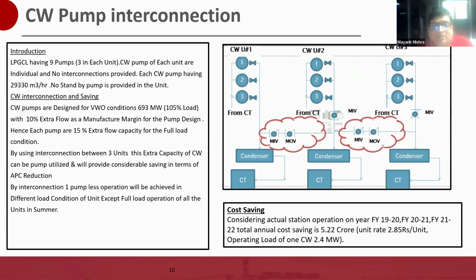We have not compromised on our condenser pressure, which is very important. Our condenser pressure is 0.08 absolute units, an economical pressure we are maintaining, which is less than our design pressure of 0.1. So there is a lot of margin available in the design. To improve efficiency and reduce our APC, we utilized that margin. This in-house modification was done entirely in-house, using materials available during the construction phase. That was a huge saving in APC reduction, approximately 0.1% station APC saved by this.